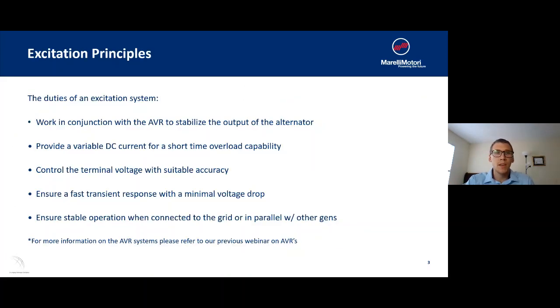Let's cover the main duties of the excitation system. The excitation system works in conjunction with the AVR to stabilize the output of the alternator. It provides a variable DC current for short time overload capability and controls the terminal voltage with suitable accuracy. This helps to ensure a fast transient response with minimal voltage drop and helps ensure stable operation when connected to the grid or in parallel with other generators. For more information on our AVR systems, please refer to one of our previous webinars that we cover, Marelli AVRs.